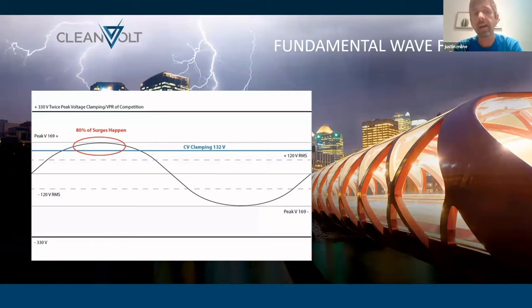And with that in mind, with 80% of the surges found within the fundamental waveform, on the current waveform, it's important to remember that when you're picking surge protection, there's a regulated term that is tested for when it comes to the performance of these devices, which is VPR, which stands for voltage protection rating, or clamping. You can even look it up on Google, what is VPR or clamping, and it will give you a 2-sentence answer about this being the level at which the surge protector wakes up and reacts to a surge.